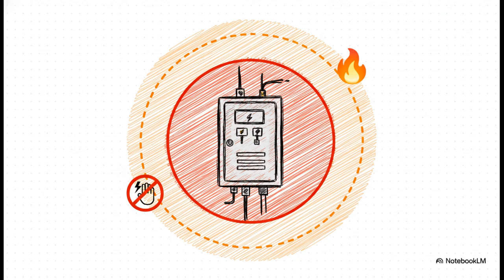When you're working on live gear, you've got to imagine invisible lines of danger around you. There are the shock boundaries, which are about keeping you from physically touching something live. But then there's the arc flash boundary, and this one can be much bigger. It's the line where, if an arc flash were to happen, you could get a serious burn.